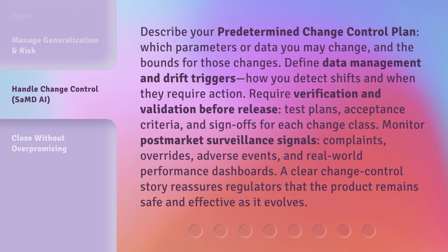Monitor post-market surveillance signals: complaints, overrides, adverse events, and real-world performance dashboards. A clear change control story reassures regulators that the product remains safe and effective as it evolves.